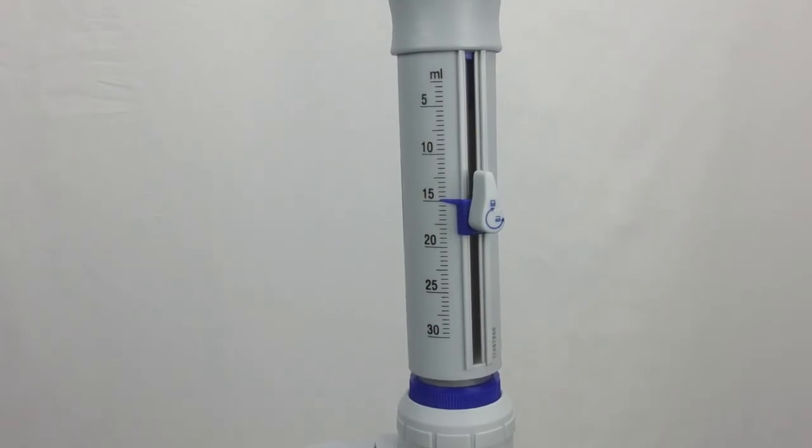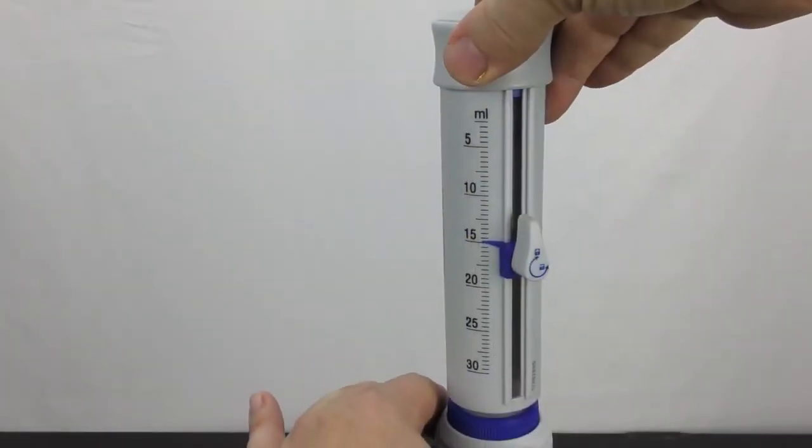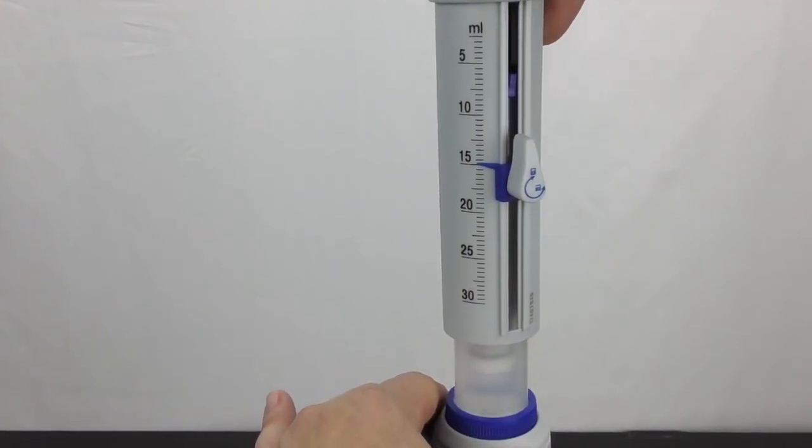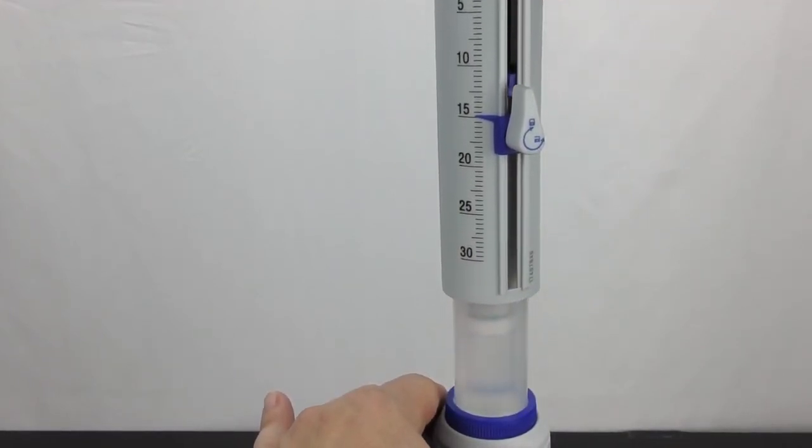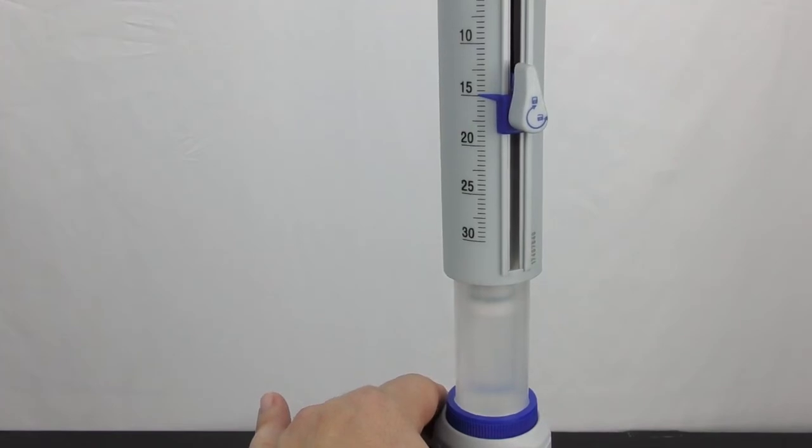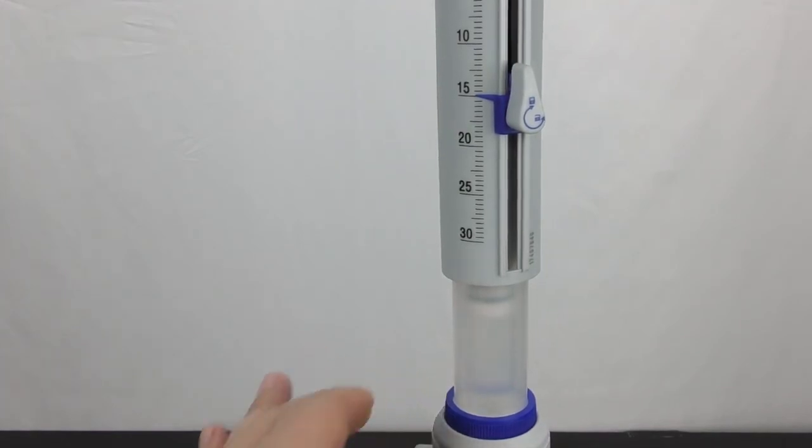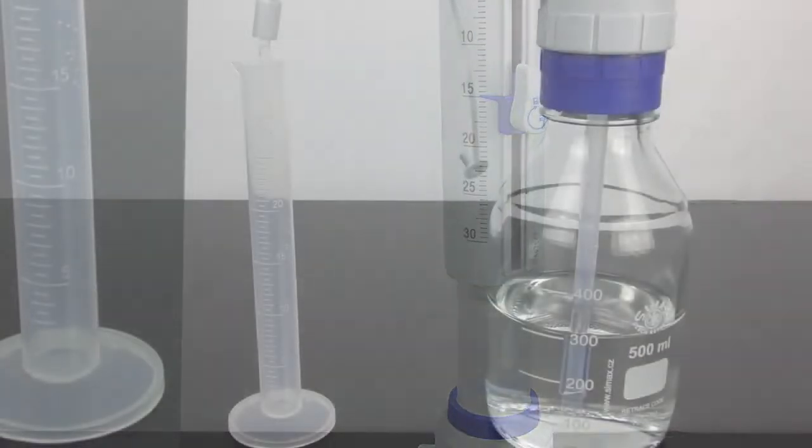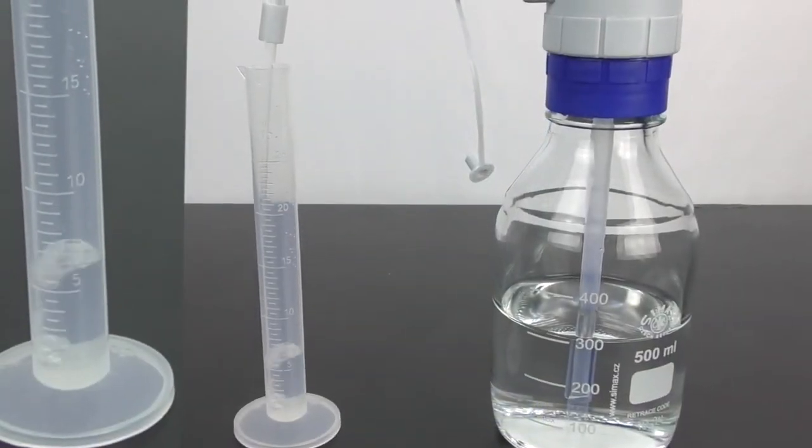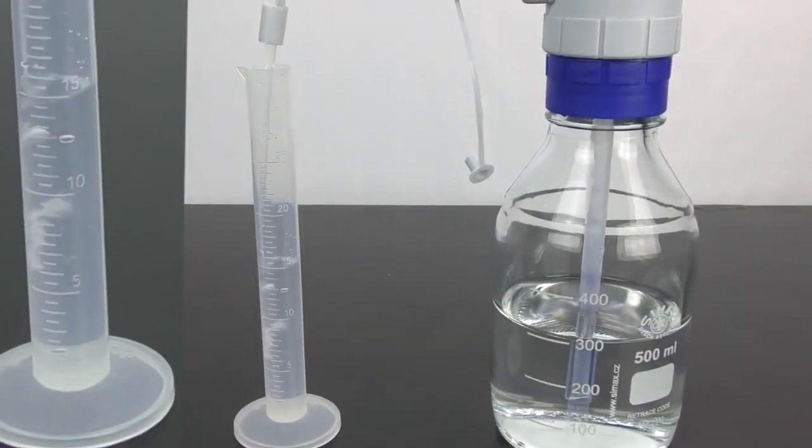I primed the pump and I had this set at 15 milliliters. I am going to pull this up firmly but gently. When you feel resistance you want to stop. That's 15 milliliters that I have pulled into the dispenser. If I simply press down I should be dispensing out exactly 15 milliliters of my solution.